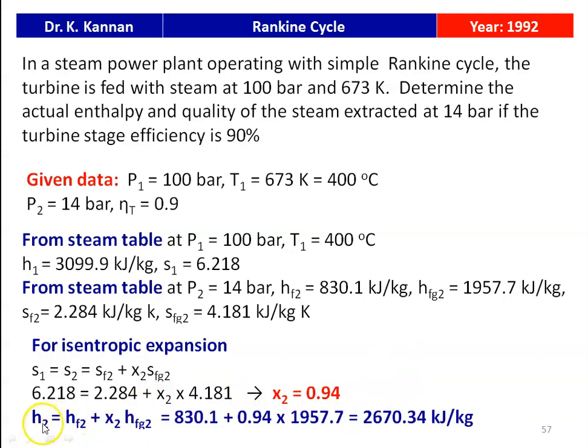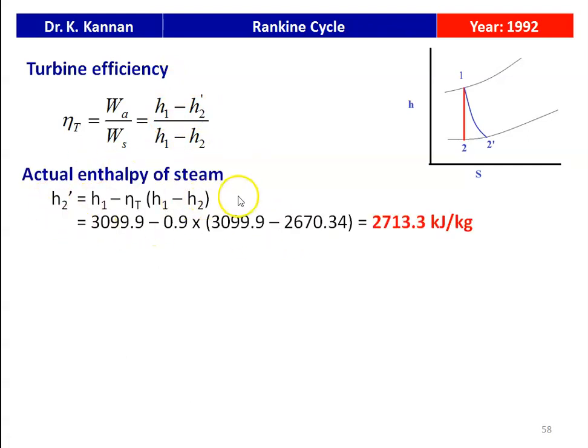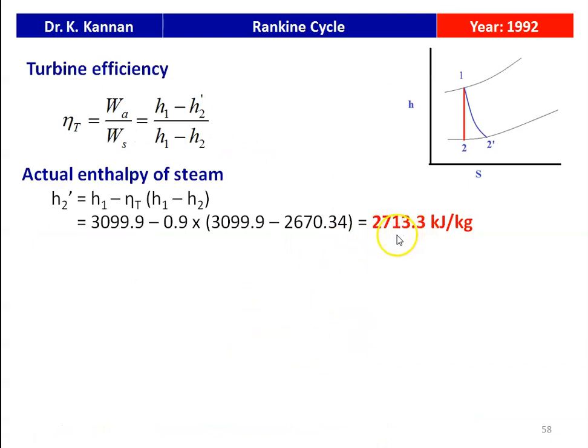The isentropic enthalpy at the turbine exit: H2 = HF2 + X2·HFG2 = 830.1 + 0.94·1957.7 = 2670.34 kJ/kg. Turbine efficiency = (H1 - H2_actual) / (H1 - H2), so the actual enthalpy H2_actual = H1 - η·(H1 - H2) = 3099.9 - 0.9·(3099.9 - 2670.34) = 2713.3 kJ/kg. Therefore, the actual quality of steam extracted is X2 = 0.94 and the actual enthalpy is 2713.3 kJ/kg.